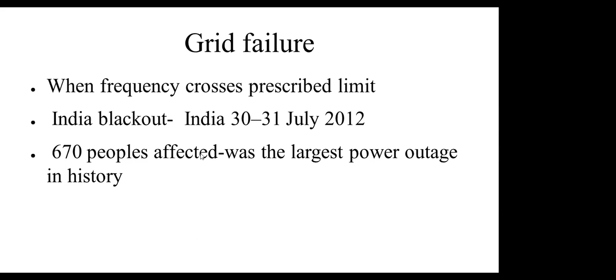If we're able to operate sections in synchronism with other sections, that's very good—if there's a problem in a particular section, you just disconnect that section and operate the others. Generally, the power system already works this way, but if generation fails in a section, the whole section is deprived of power. If you have a power junction in that section that can supply without problem, that's a very good solution—and that's one way we can move toward microgrids.